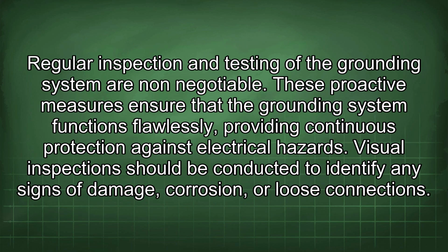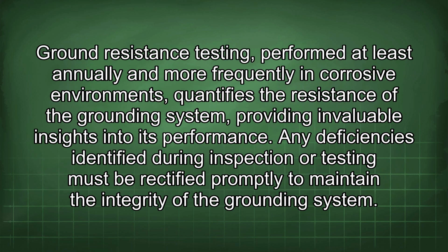Regular inspection and testing of the grounding system are non-negotiable. These proactive measures ensure that the grounding system functions flawlessly, providing continuous protection against electrical hazards. Visual inspections should be conducted to identify any signs of damage, corrosion, or loose connections. Ground resistance testing, performed at least annually and more frequently in corrosive environments, quantifies the resistance of the grounding system, providing invaluable insights into its performance. Any deficiencies identified during inspection or testing must be rectified promptly to maintain the integrity of the grounding system.